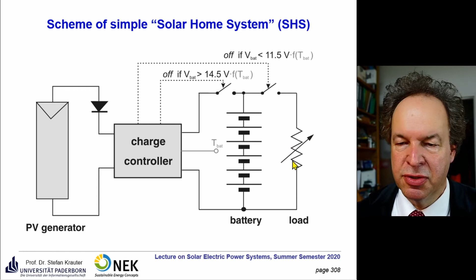This is just a quick calculation. For example, you've got a daily consumption of 400 watt hours per day—this is just load and times of use. If you have a light bulb of 10 watts used for 5 hours, that's 50 watt hours. For 400 watt hours, in this sunny location, you need a panel size of about 125 watt peak.